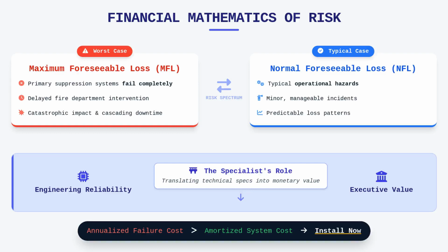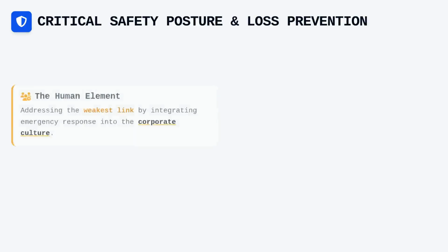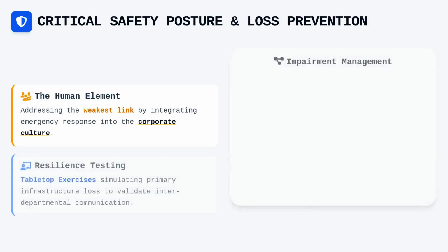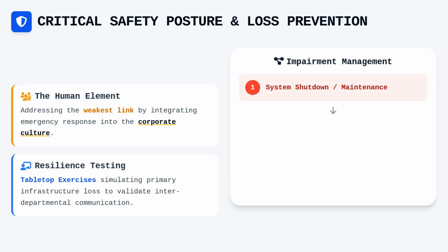Maintaining this safety posture requires meticulous attention to the human element, which often proves to be the weakest link in any loss prevention program. A robust impairment management scheme is non-negotiable. You must have formal procedures governing the temporary shutdown of protection systems during maintenance or impairment events. If a sprinkler valve is closed for repairs, an auxiliary strategy, such as a fire watch or pre-planned temporary protection, must be triggered immediately.